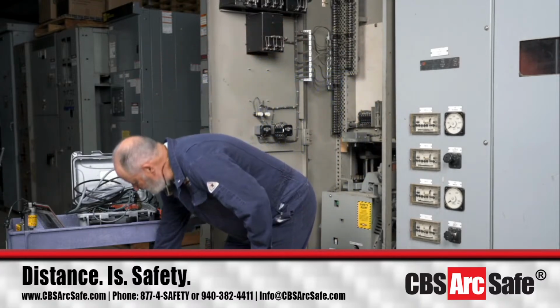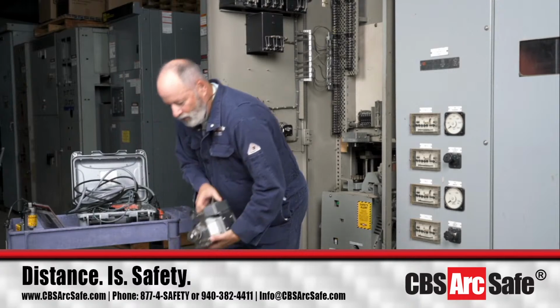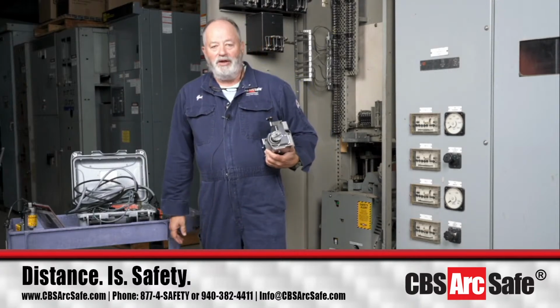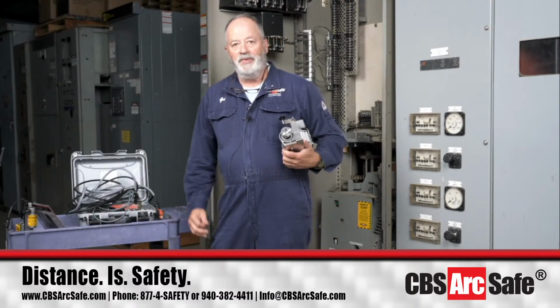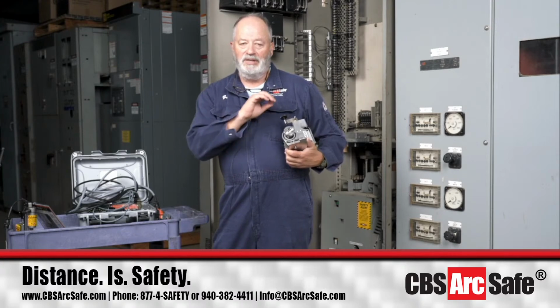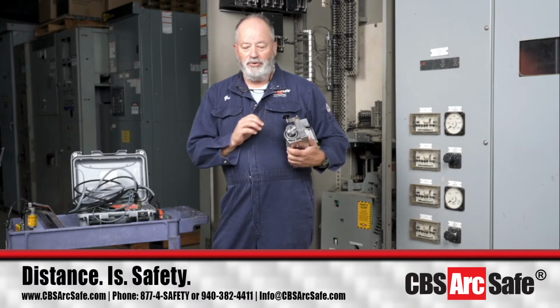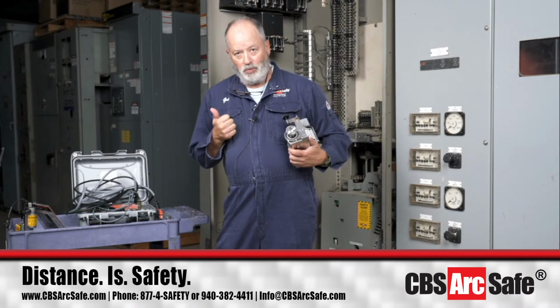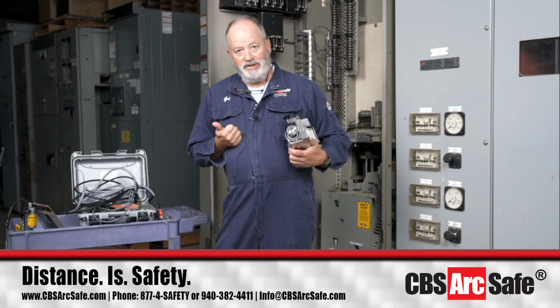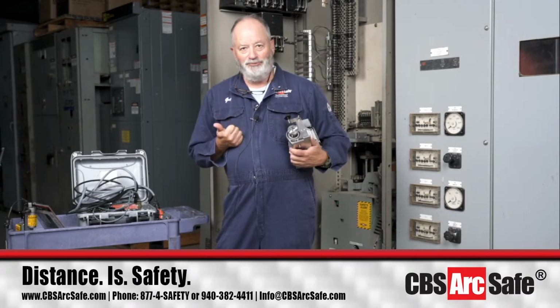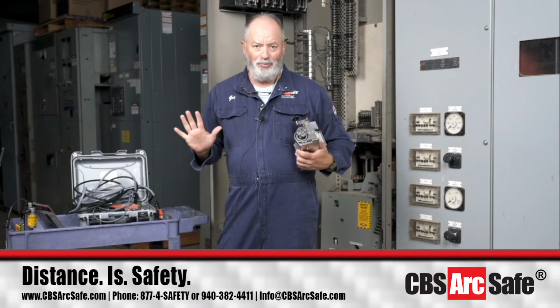So the first thing is we have our motor. Our motor is wound for 120 volts DC. One of the things to understand is this: in the Magnablast switchgear, you can have 48 DC, 120 AC, 120 DC, 240 AC, 240 DC. So you've got 5 different control powers.